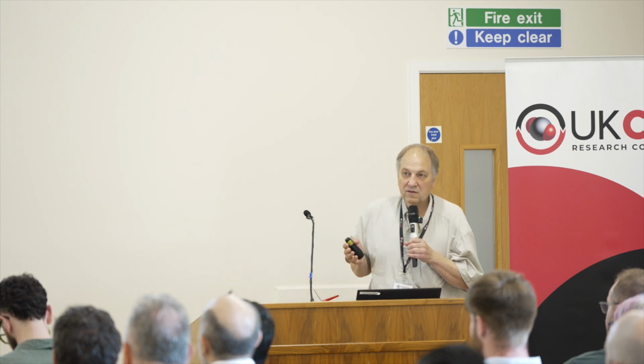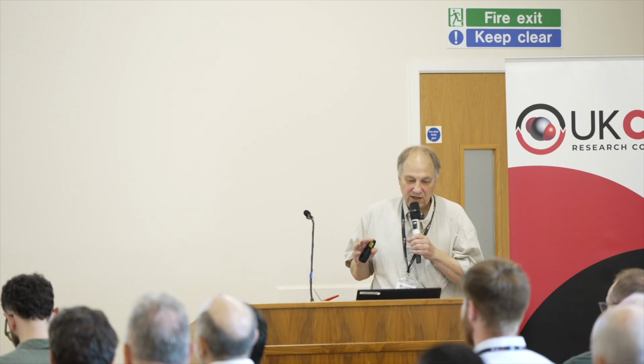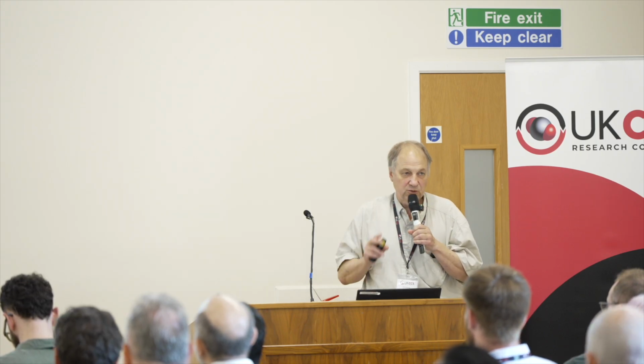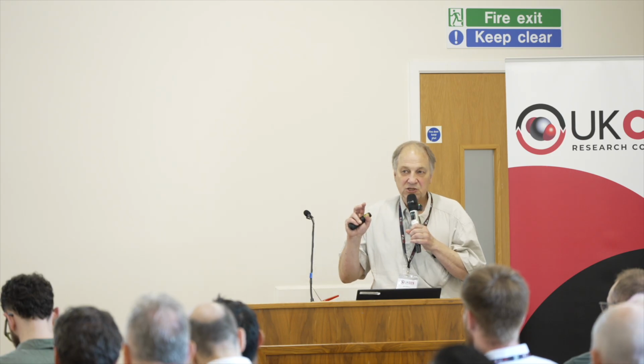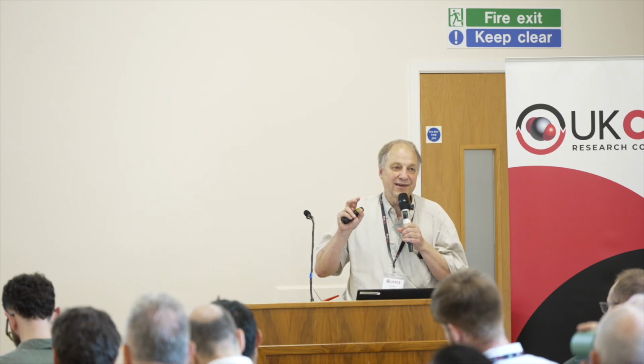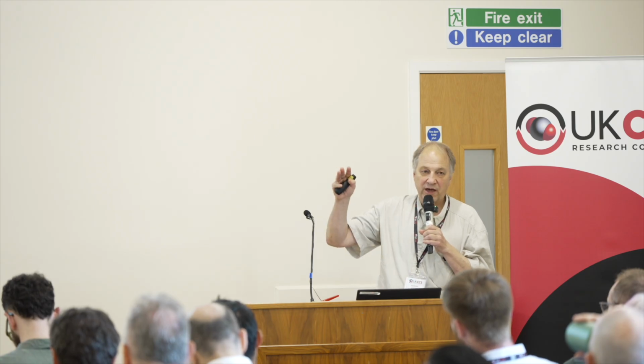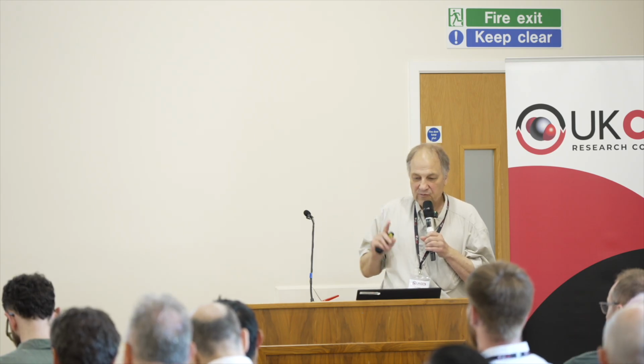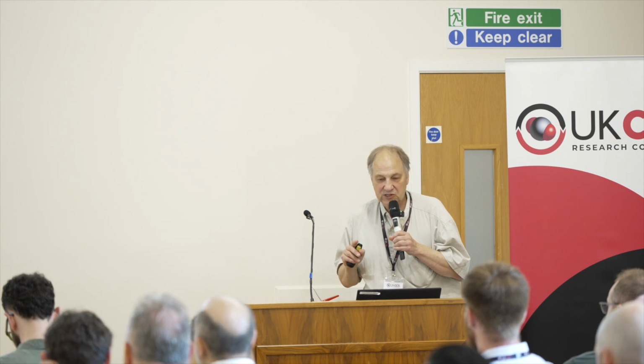So that's the bit where you're driving it. And then the red line is the temperature in the middle. You can do some cross correlation, and Aisha Ibrahim, who's here somewhere, I think, did this, and you can show that they follow each other as you'd expect, because both are related to the lean loading. But there's 5 minutes between them, and that gives you some idea of the thermal lag in the system. It's a combination of the steam getting up there and just things getting warmer. So that's 5 minutes. Still relatively fast, and fast enough to do control.